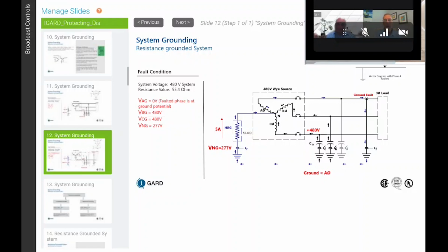And conversely, there's a lot of loads right now that are not 277 volts, but a lot of the LED lighting are coming out with 240, 480 volt LEDs. Everything can use a resistance grounded system. So it depends on whether you're going to use that neutral or not. For 120/208, you have a distributed neutral. I wouldn't put in a resistance grounded system. All right, thanks.